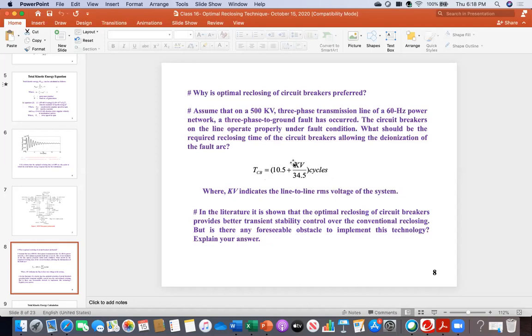So this conclusion, as I said, is an empirical equation for engineers. I think this equation was first developed somewhere in Europe — they explored it and said this can be applicable to any system. It just depends on the system kV, the number of cycles, and the frequency of that country. That's why you see these magic numbers, 10.5, 34.5, because after a lot of trial and error over several years, they converted this into an equation.